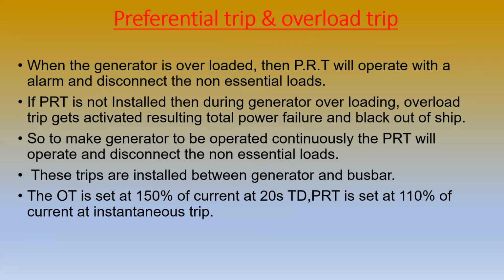These trips are installed between the generator and the bus bar. The overload trip relay is set at 150% of the current with a 20 second time delay. And the preferential trip relay is set at 110% of the current as an instantaneous trip. Immediately it will trip at 110% of the current value. So if that current value is present, the preferential relay will trip. An electromagnetic coil is kept, and if that coil senses more than 110% of the current, it will be an instantaneous trip. So that is the PRT.